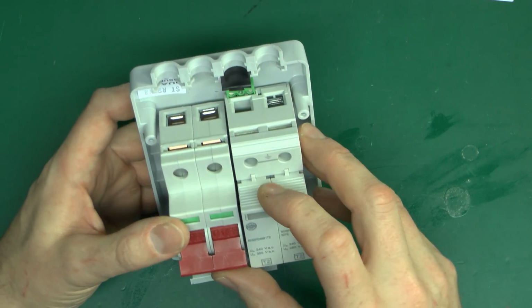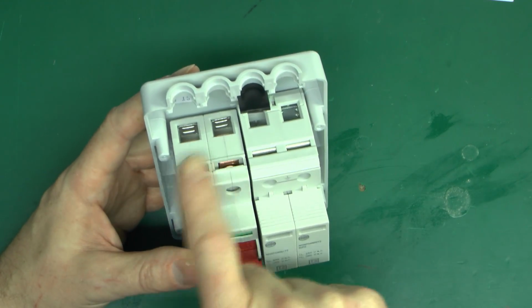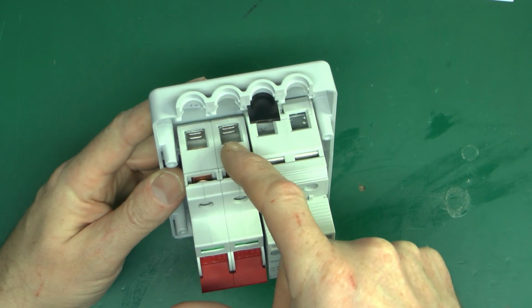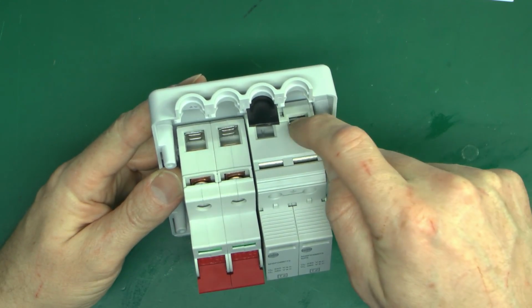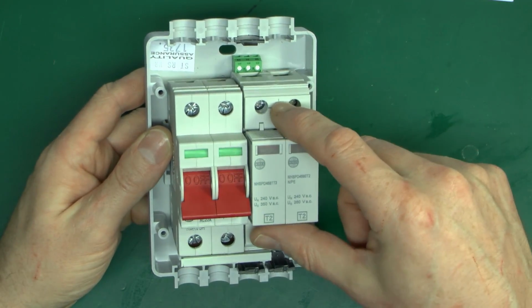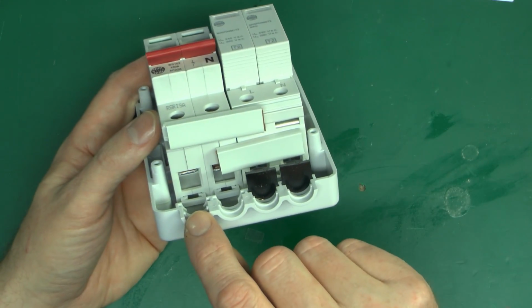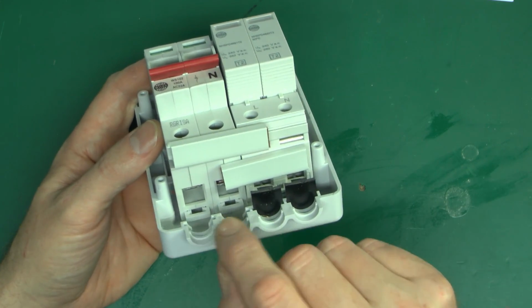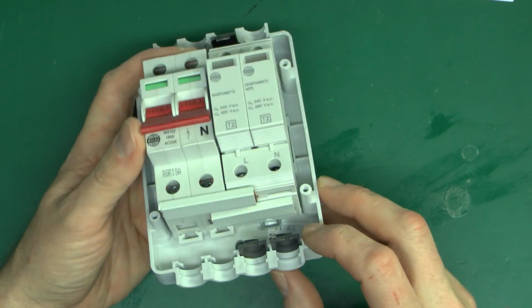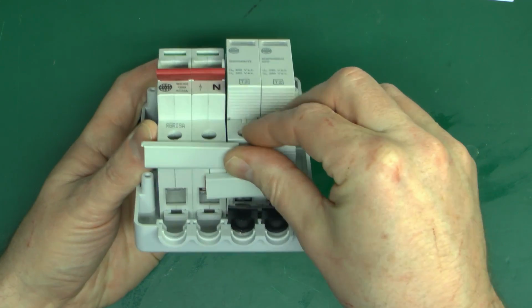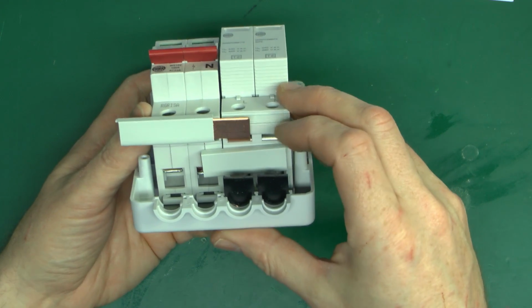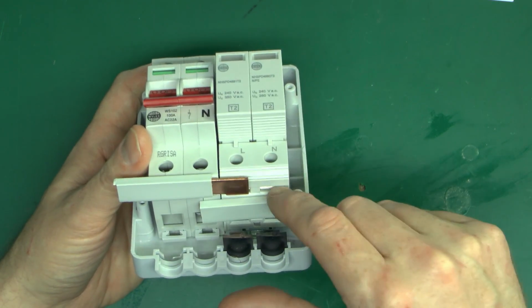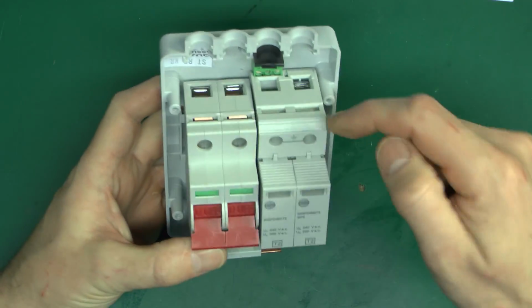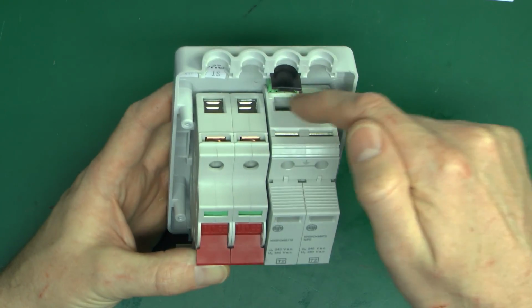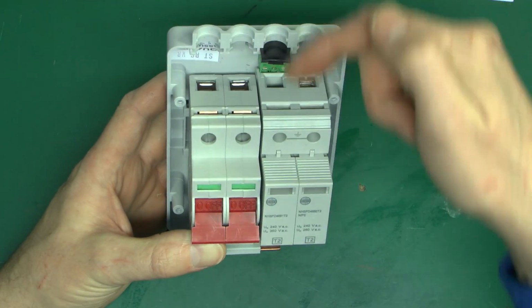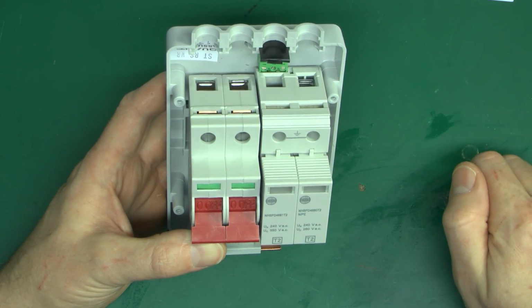And have a look at this Wylex example. Your supply would come in the top here, so line and neutral coming in the terminals here just on the isolator. Earth connection goes in the top there, as marked here. And then at the bottom here is where your supply continues to your installation, so obviously controlled by the isolator. And we've got these bars that come across. Just slide that away, it's just the copper underneath. So line and neutral come across to the device, and then your earth connection, so it goes on the top, and your outgoing earth connects to the other terminal there. So again, that's the same as that sort of point wiring that we saw in that diagram.